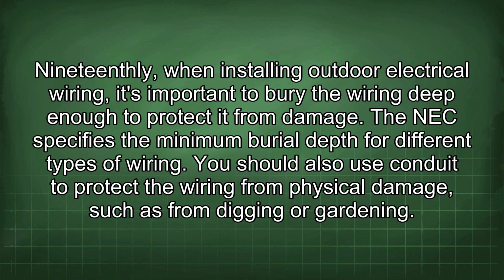19thly, when installing outdoor electrical wiring, it's important to bury the wiring deep enough to protect it from damage. The NEC specifies the minimum burial depth for different types of wiring. You should also use conduit to protect the wiring from physical damage, such as from digging or gardening.